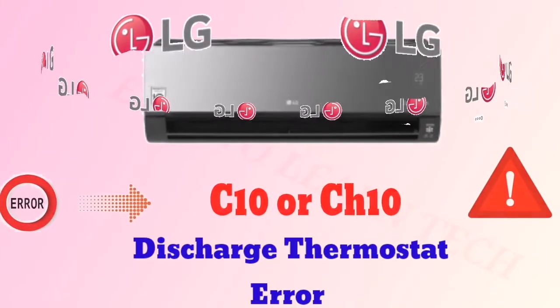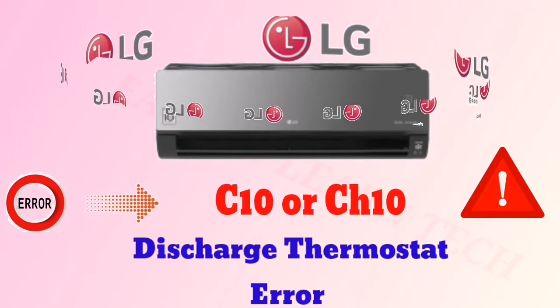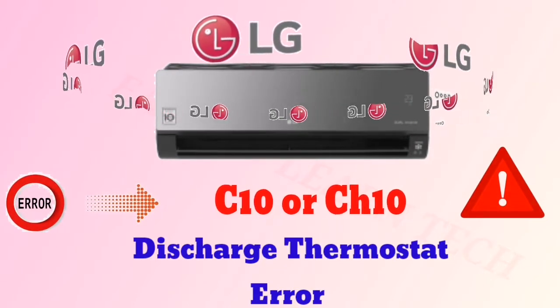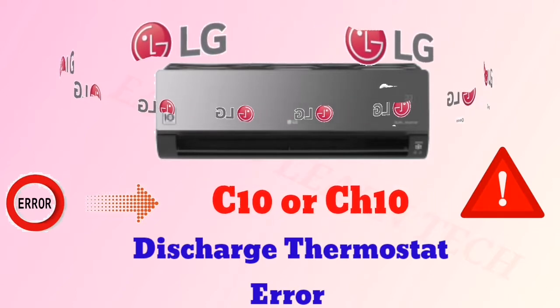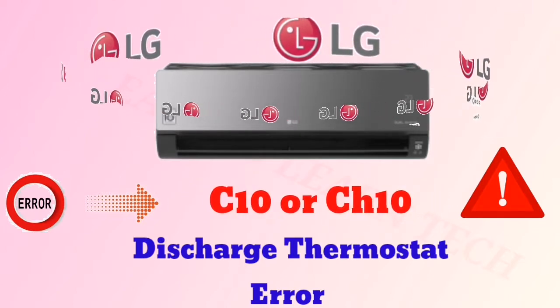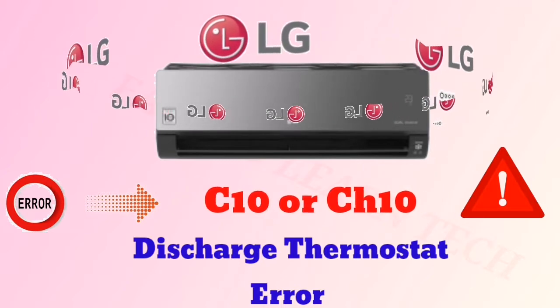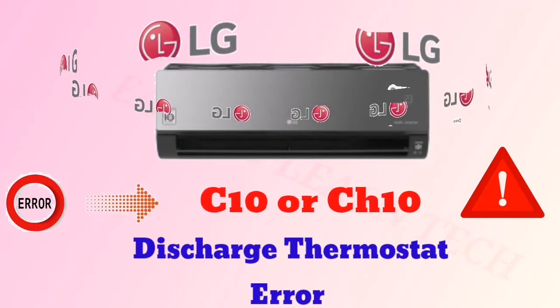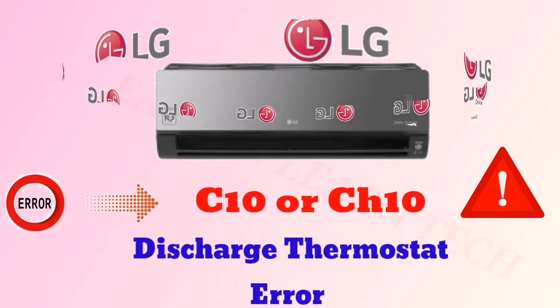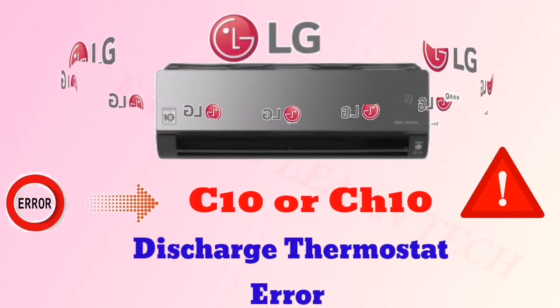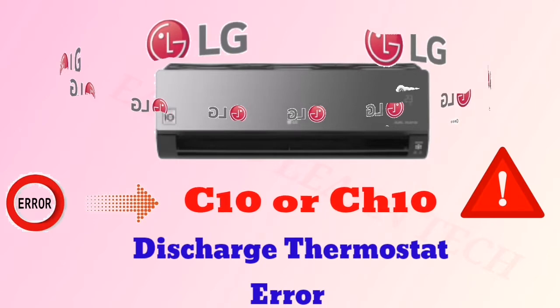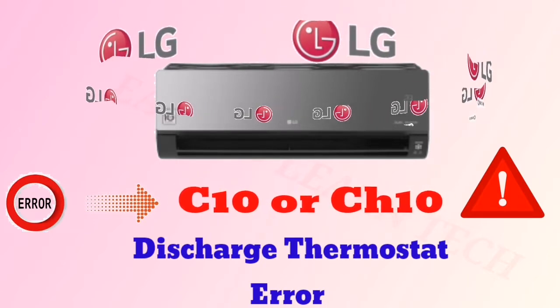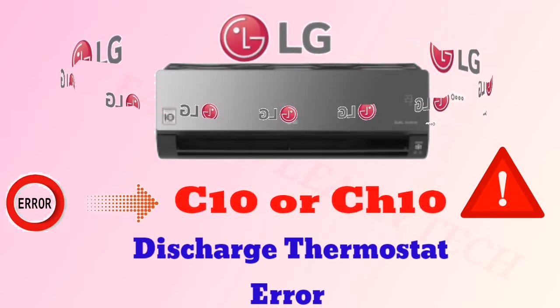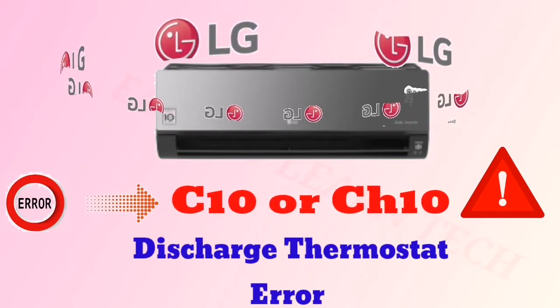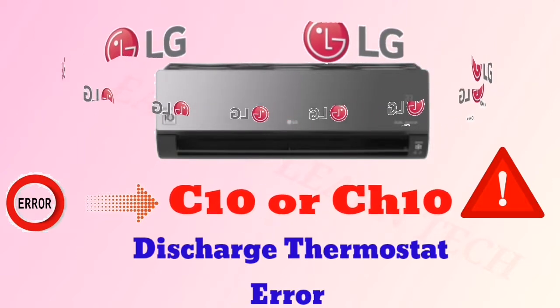Let's see the next error code, C10 or Ch10. It means discharge thermistor error. This sensor can be found in our outdoor unit, installed near the discharge pipe. First of all, you have to check the placement of this sensor. If the placement is not good, place it in a proper place. And if the placement is good, then you have to check the resistance of your thermistor. If the resistance is not good, then you have to change the sensor. If the resistance is good and it is still showing the same error, then you have to check your PCB. And if your PCB is faulty, you need to replace the PCB. Your unit will be in working condition.